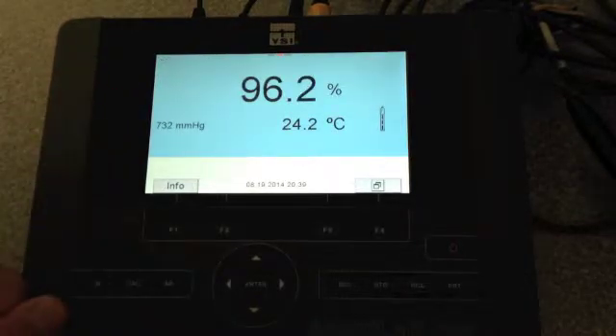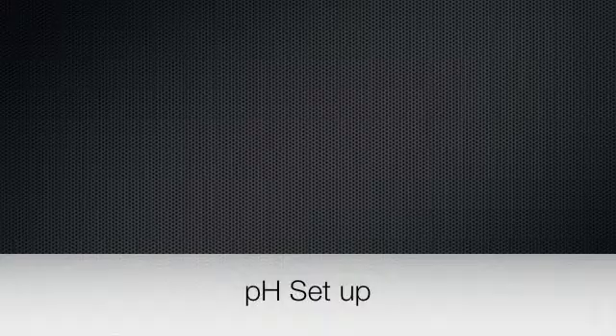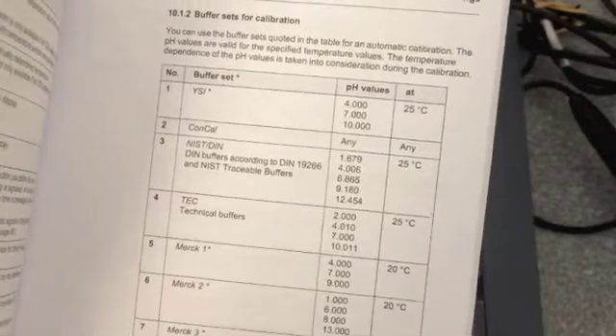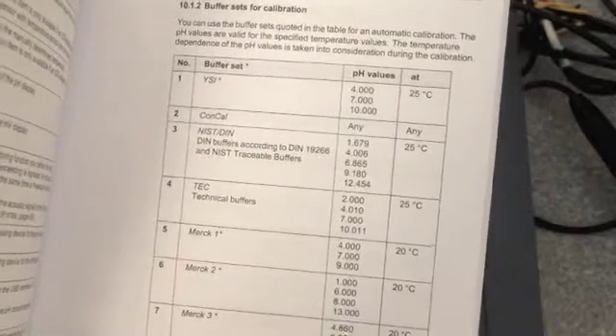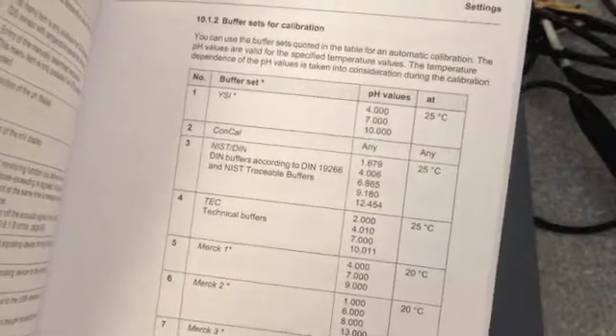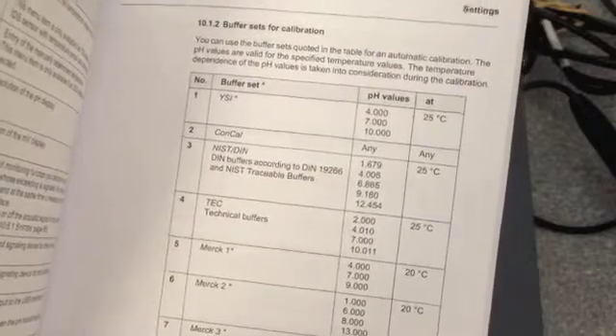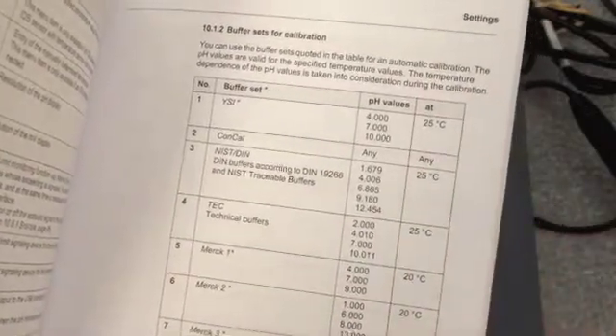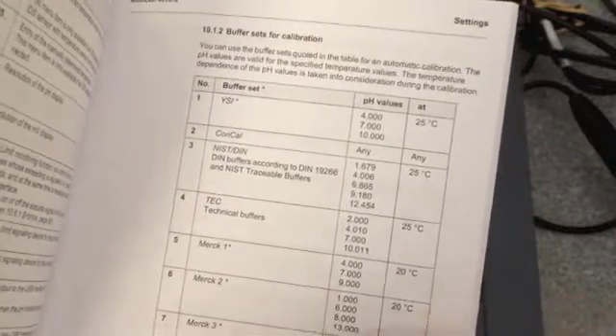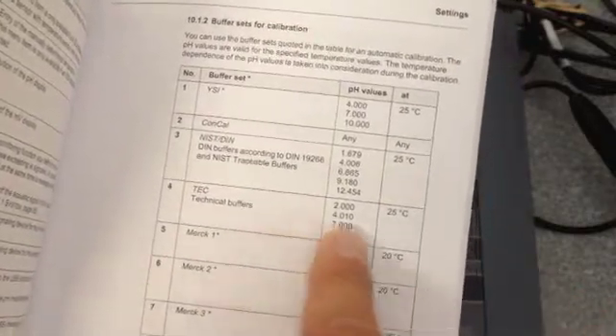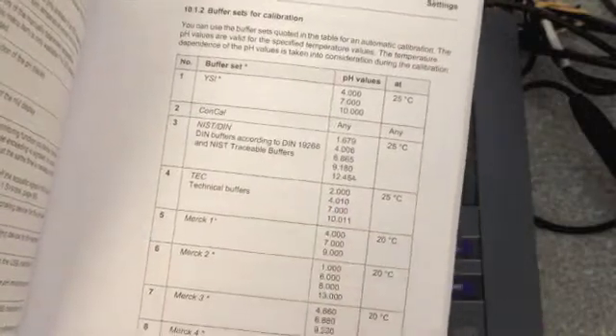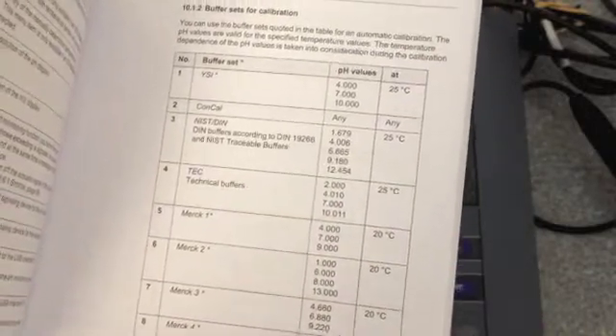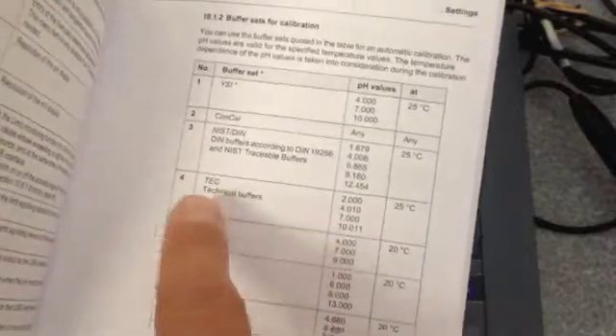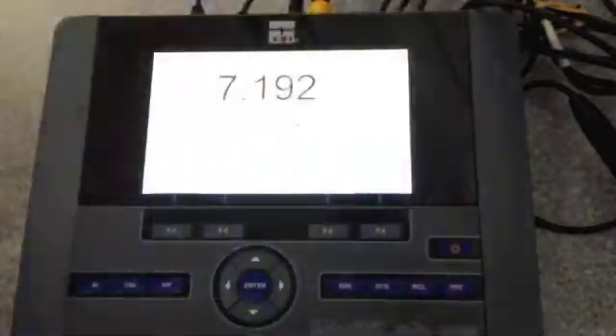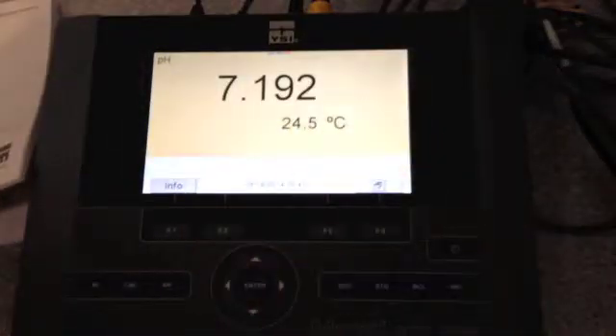I'm going to hit continue F1, and right away we're back in your manual. It lists all the buffer sets that this meter will recognize, and the default buffer set is the YSI buffer set, and that includes pH values of 4, 7, 10. But let's say, for example, you are using technical buffers, and that includes pH of 4.01. So if we wanted to change the buffer set, we're going to be back into the pH mode.